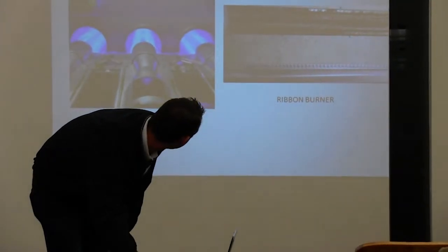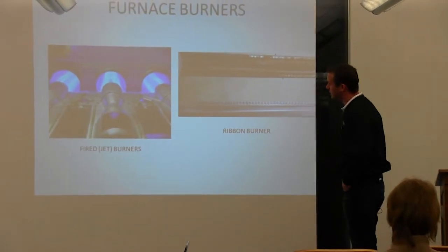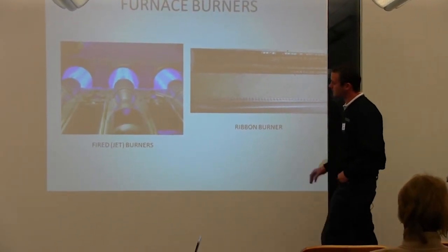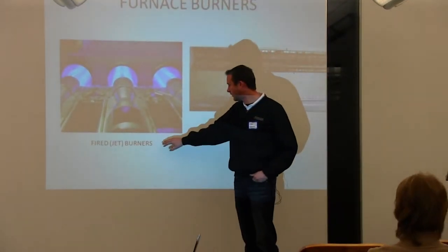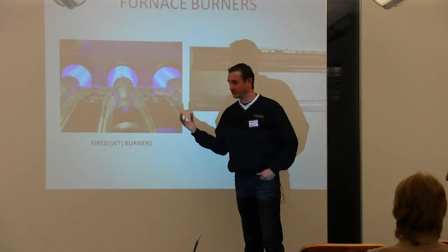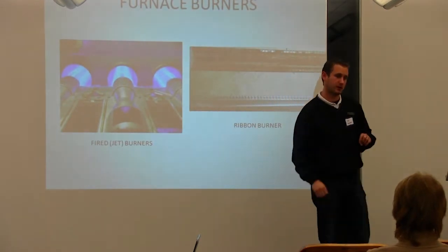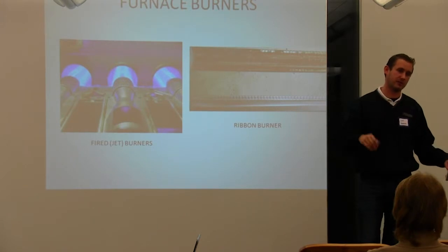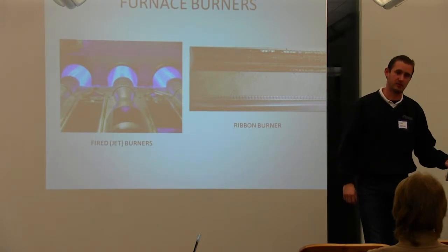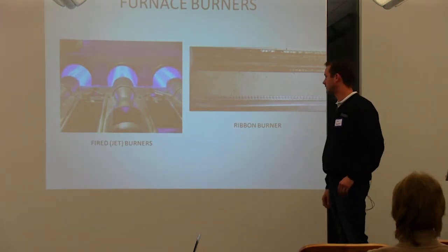So the next step is we clean and adjust your burners. Furnaces now have 2 types of burners. The most common one is going to be a fired or a jet burner. It's just a little cone, and it sprays gas through there, and it mixes with air, and then it combusts on the other side of these cones.